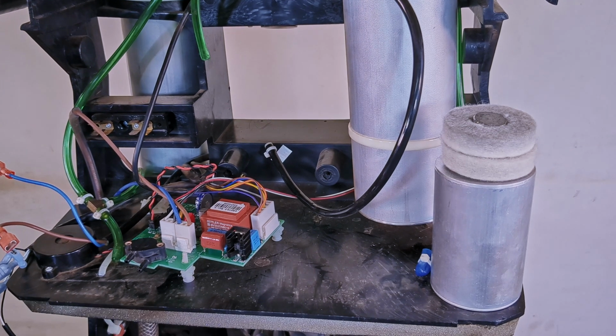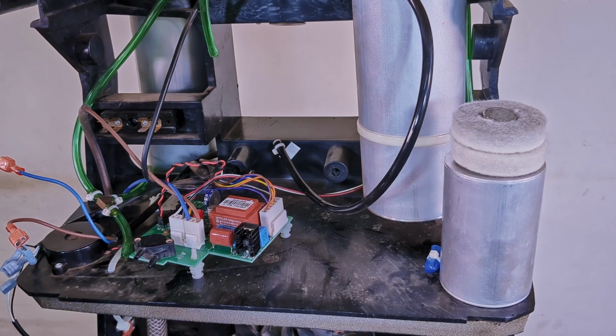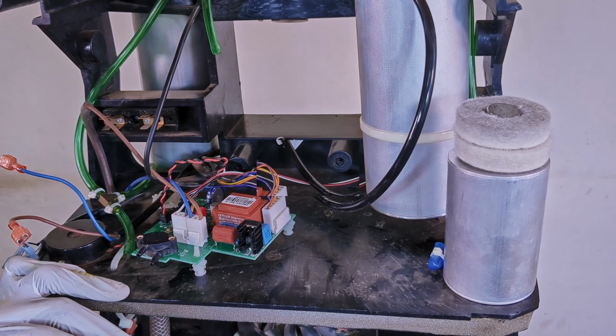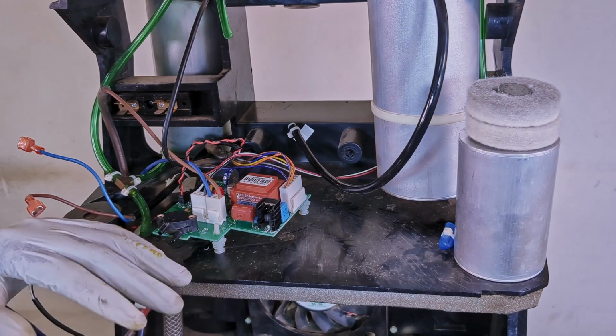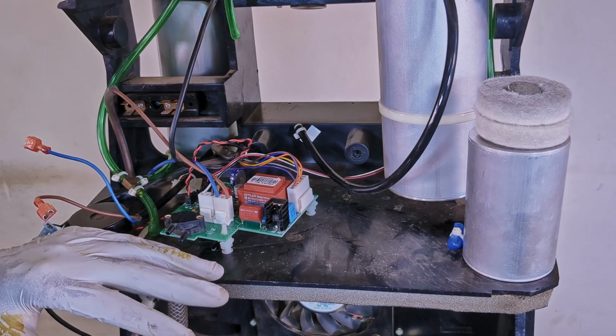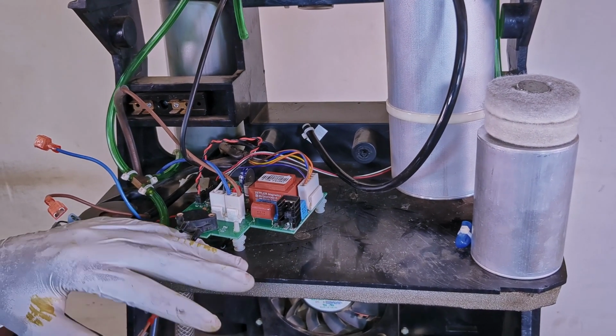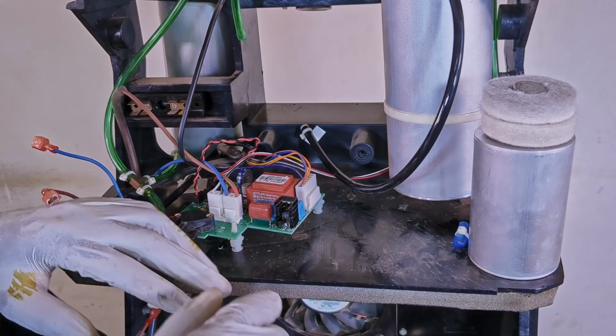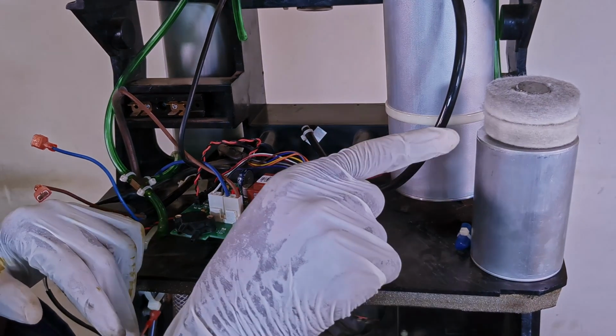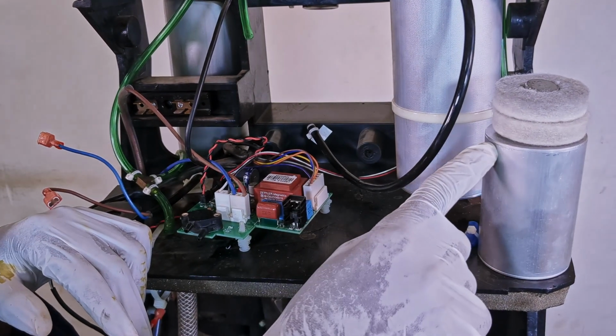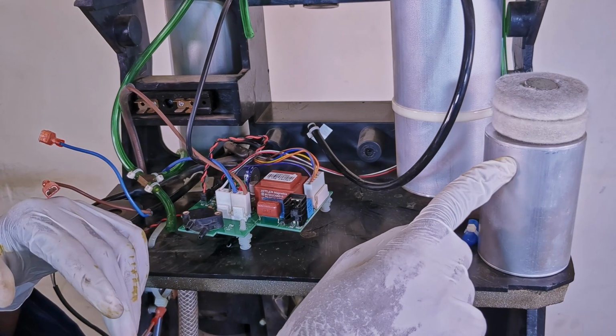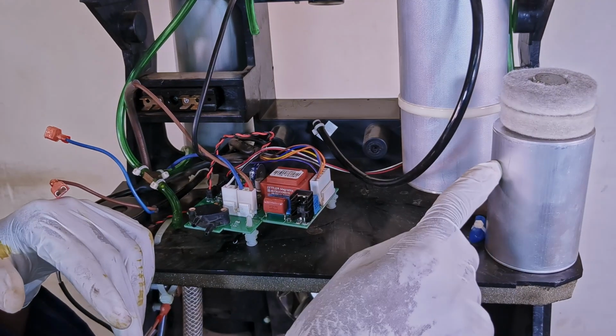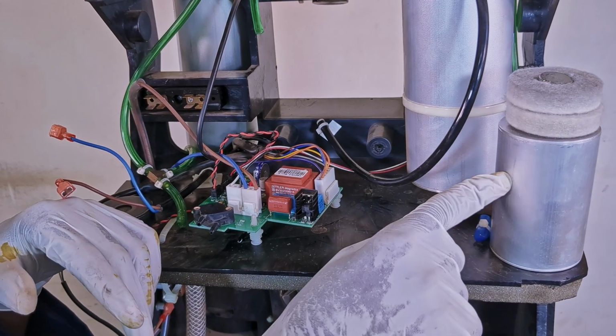Now, let us look at the pneumatic system of this oxygen concentrator. Air enters the unit through the gross particle filter, which filters out dust and other large particles. After that, air passes through the fine particle intake filter. This one further removes impurities and small particles from air before it proceeds to the compressor.